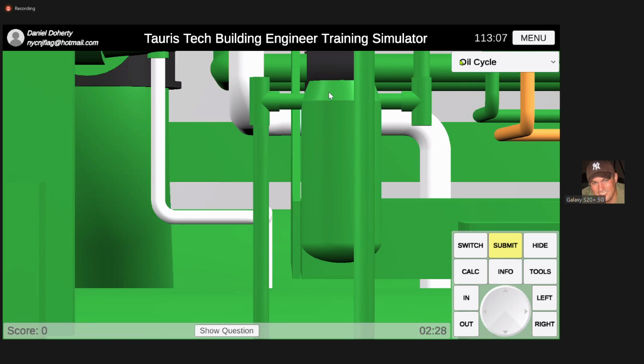On Metrotech, on the bottom of this filter, there's a little black T, and that's your drain valve. So if you wanted to change out this cartridge, they also call the cartridge oil cartridge. Compressor oil cartridge is the same thing as a compressor oil filter. So you would isolate this, front seat this, front seat this, and open up your drain because now you're relieving the pressure from the filter. Then you can unscrew it, take out the old filter, put in a new filter, close your drain, and then you would backseat this and backseat that. And now your filter's back in operation, all ready to go.